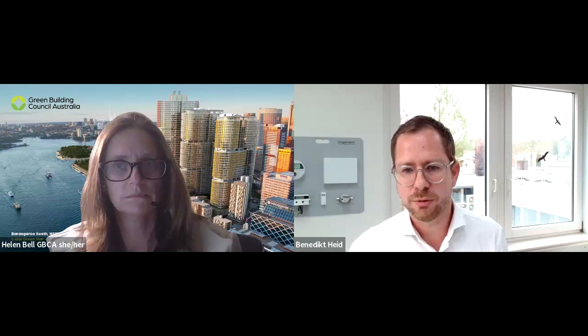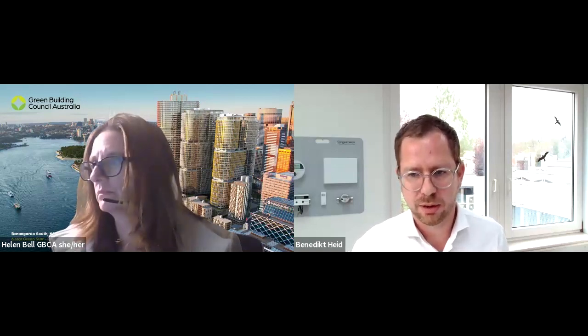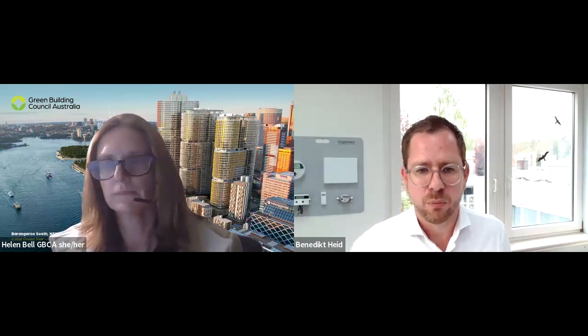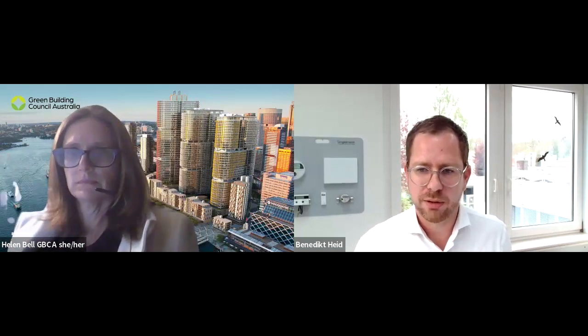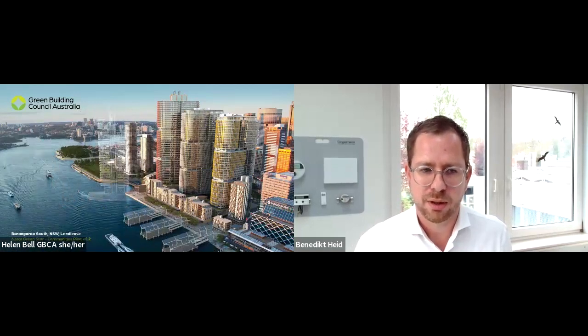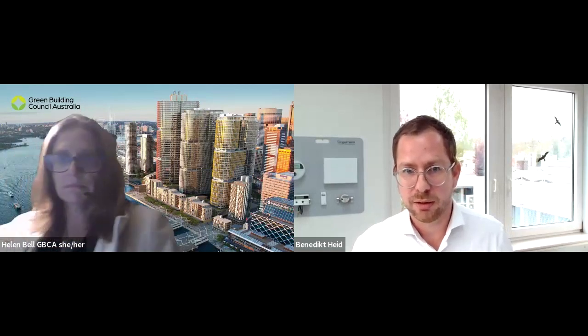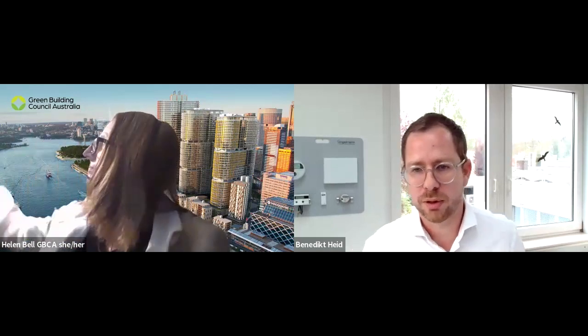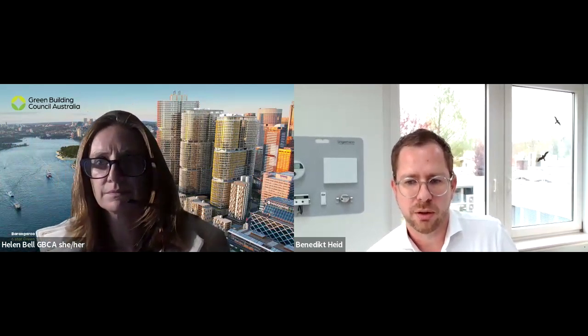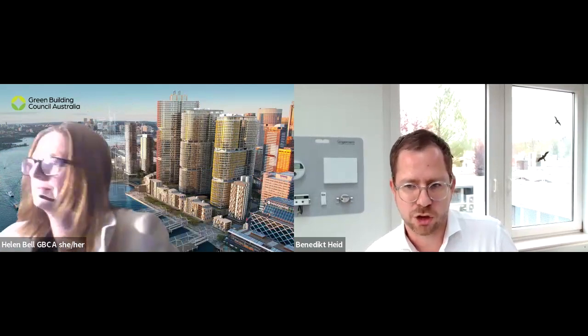What we basically do is measure the temperature on the inlet side and the outlet side of a centralized cooling or heating system with temperature sensors, and we also measure the flow. Having these two pieces of information - the delta T from the inlet and outlet side, plus the flow of water being used for heating or cooling - we are able to determine how much thermal energy was spent in this specific application.